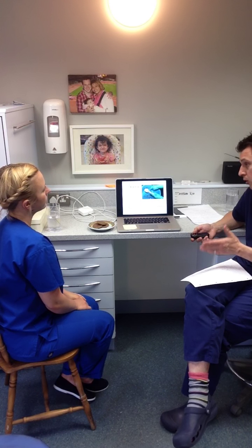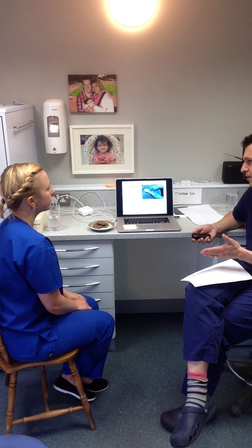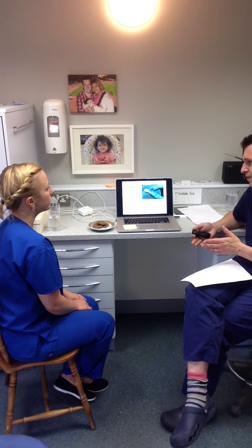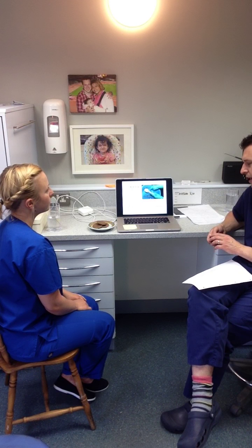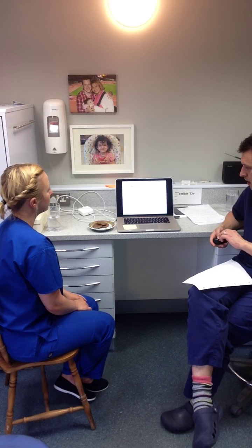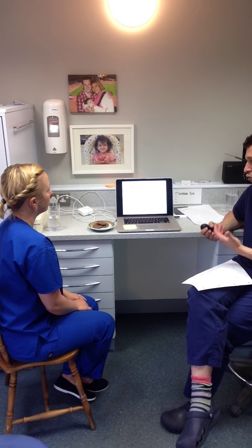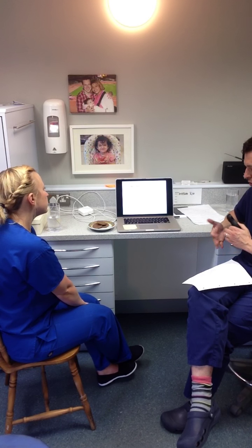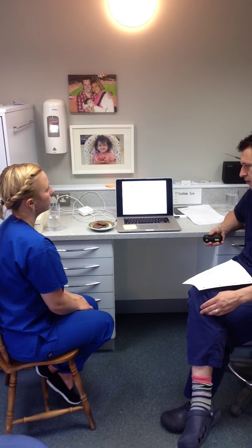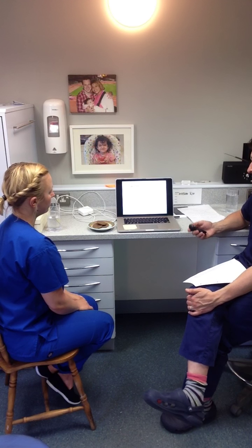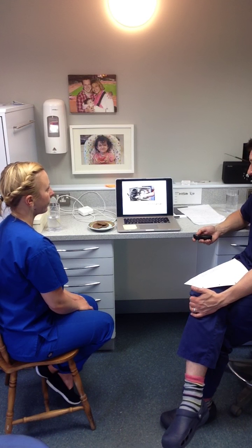The washer disinfector takes a long time as well. You're talking a good 10 to 15 minutes for a cycle, and in the grand scheme of a sterilisation cycle, it just adds a lot of time on, and there's no proof that it's actually effective. So once the cleaning has taken place, you've got to inspect the instruments, discard any defective ones, and inspect them under magnification to ensure you've effectively cleaned them. Make sure all the debris, blood and gunk are off. Handpieces should be adequately, but not excessively, lubricated prior to sterilisation.